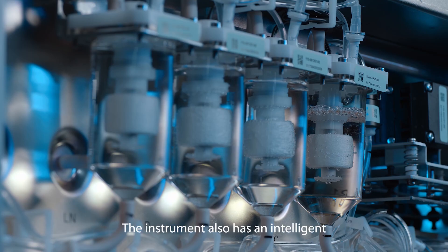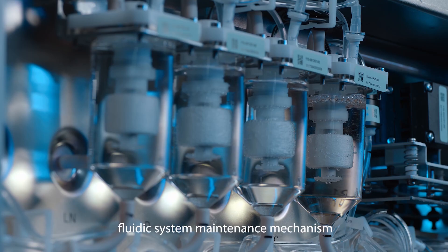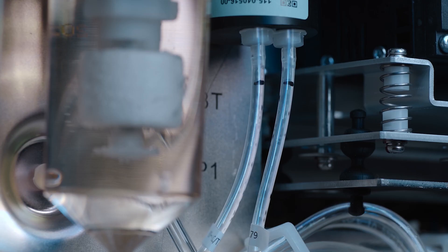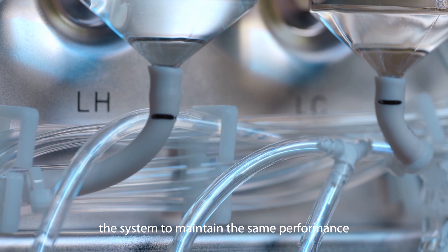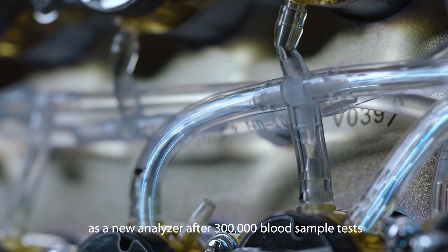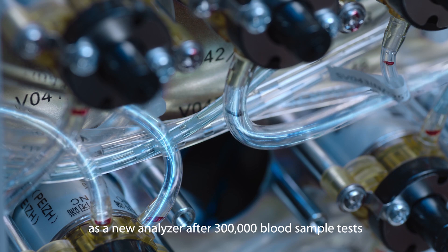The instrument also has an intelligent fluid system maintenance mechanism. Its reliable fluid workflow enables the system to maintain the same performance as a new analyzer after 300,000 blood sample tests.